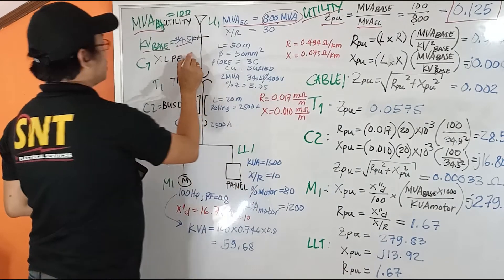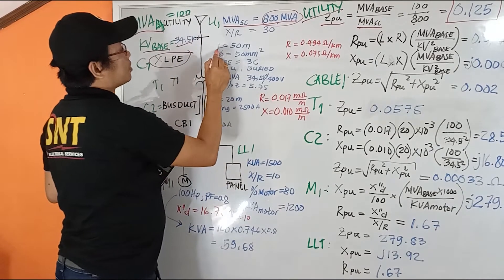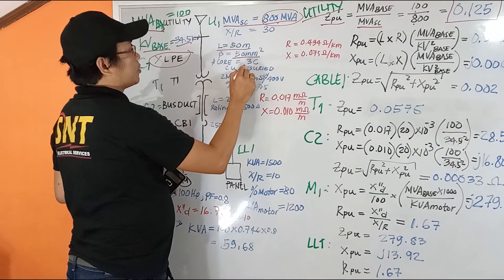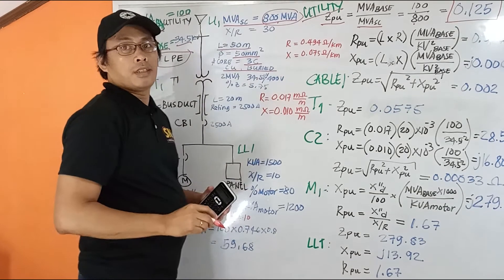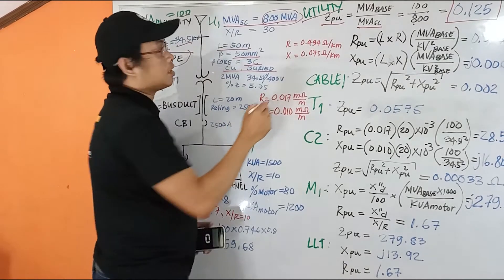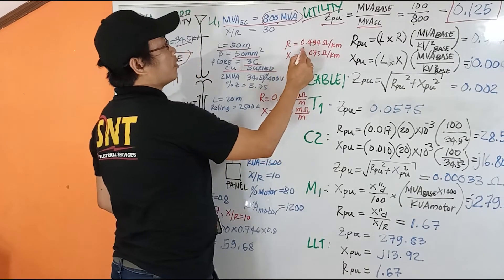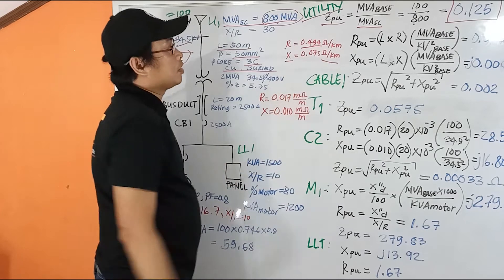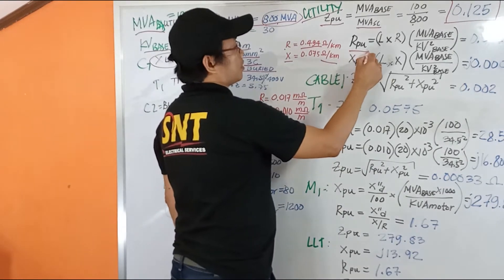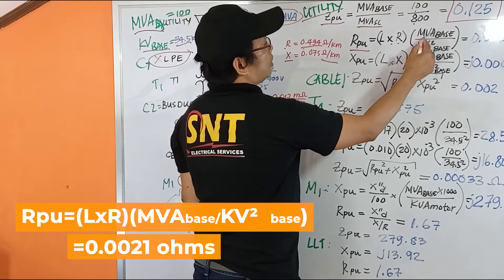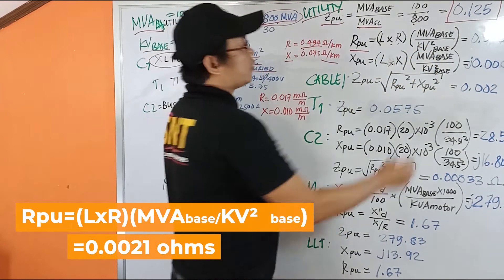Now for our cable here, the XLPE, we are given the distance of 50 meters, the diameter is 50 mm squared, and we have three core copper and buried. So after getting this, we came out with the data of the resistance at 0.494 ohm per kilometer and reactance of 0.075 ohm per kilometer. So we get the resistance per unit: length times the resistance given times the MVA base over the kV base squared. And we get this value.